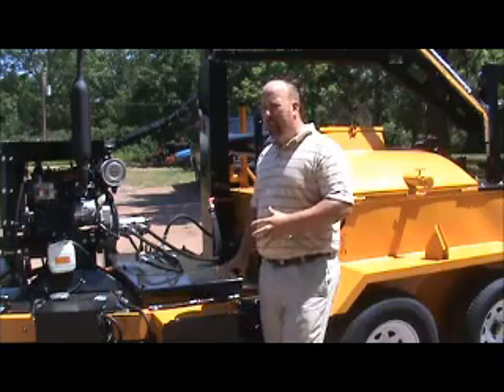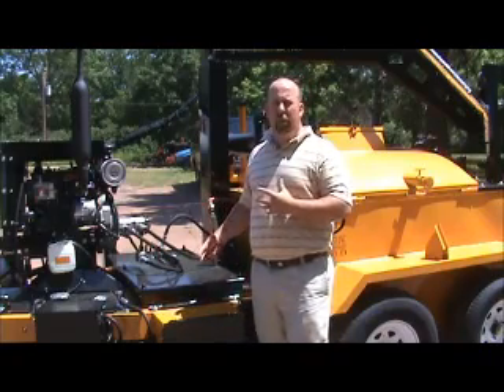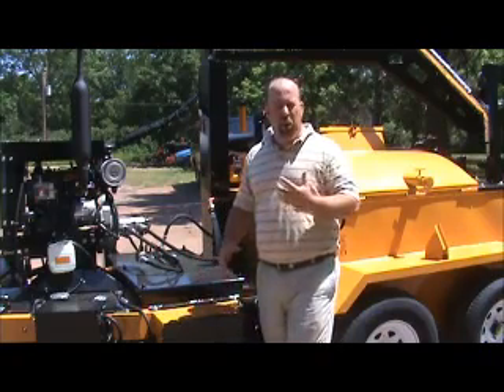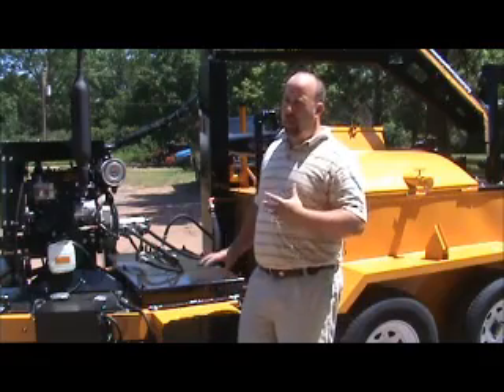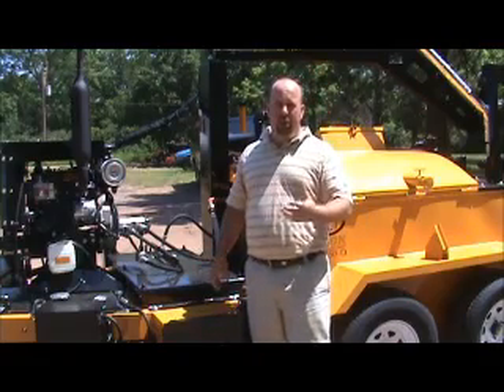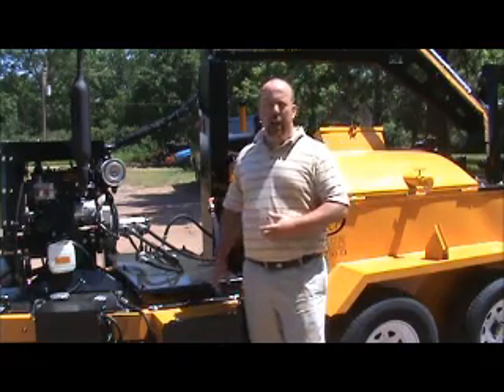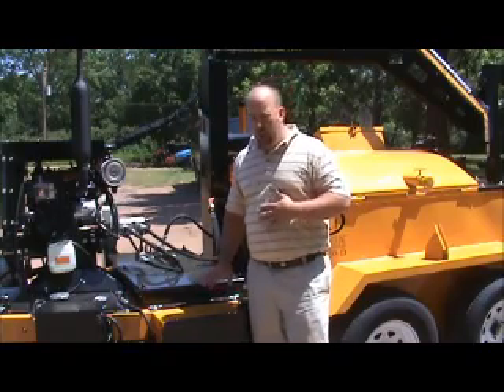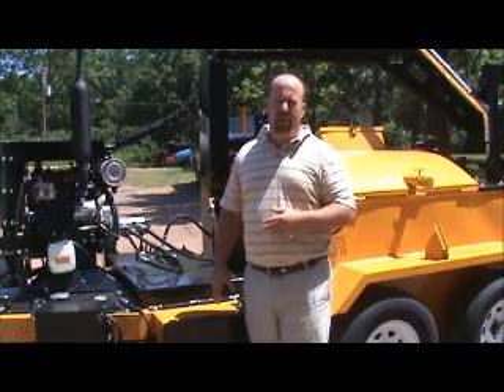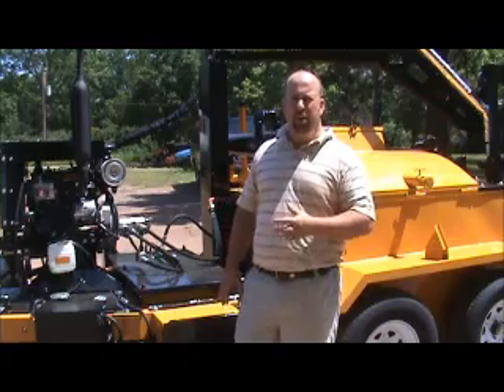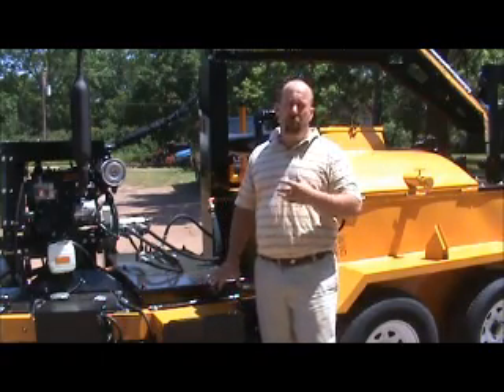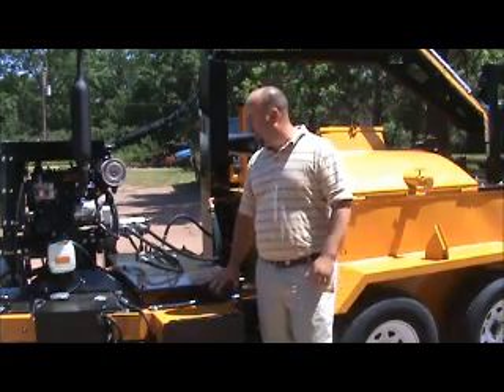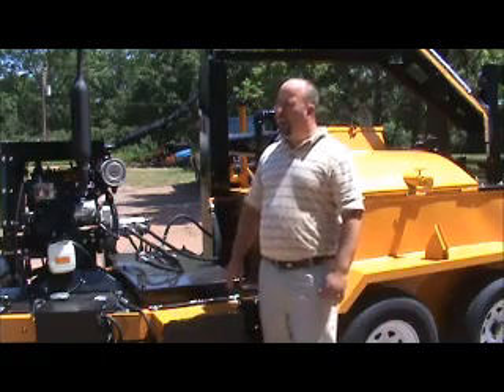If you don't replace the liner in this, you'll actually burn the coil down. It'll get so hot inside there that we can melt the coil. So it's very important that we have a good stainless steel liner in it. That's a replaceable part. It's a maintenance item. General rule of thumb is you can get somewhere between 600 to 1,000 hours out of that stainless steel liner, but we still want you guys to inspect that liner inside the box.